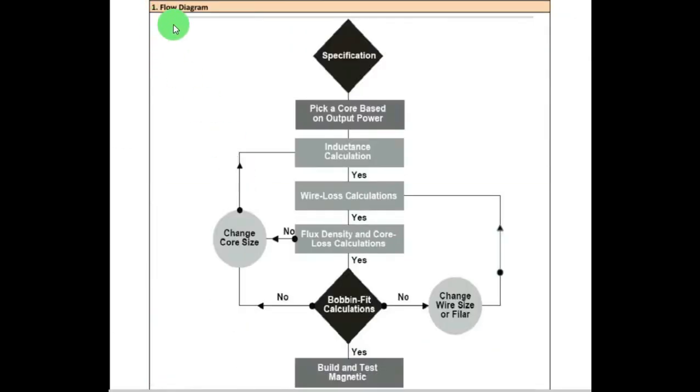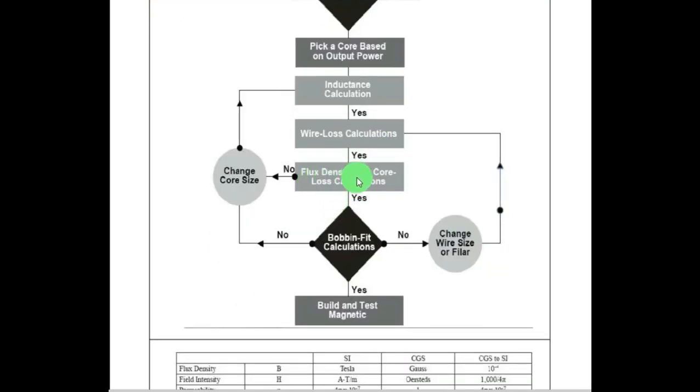So the first step of transformer design is to understand the flow diagram. You can see here, to start the flow diagram we need to have the specification, that is called the design specification. Then you need to pick a core based on output power. Then you calculate the inductance value, and then go for the wire loss calculation, and then flux density and core loss calculation. At this stage, if you find that your flux density is more, you have to reiterate.